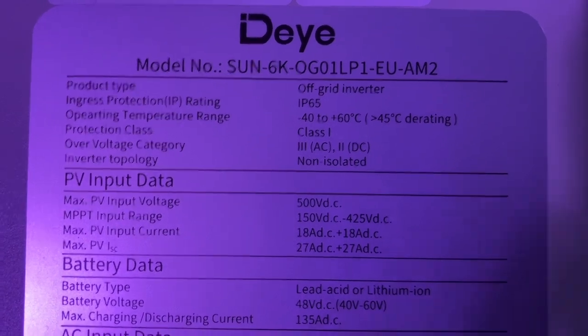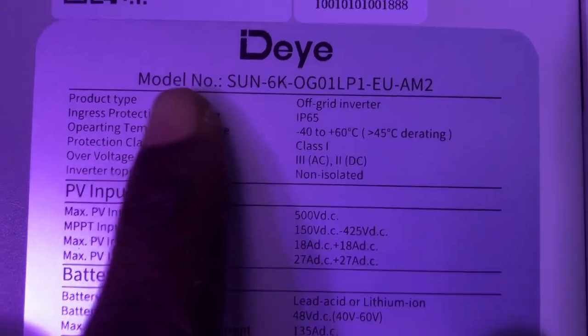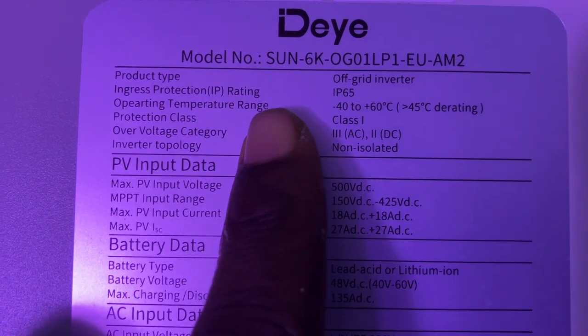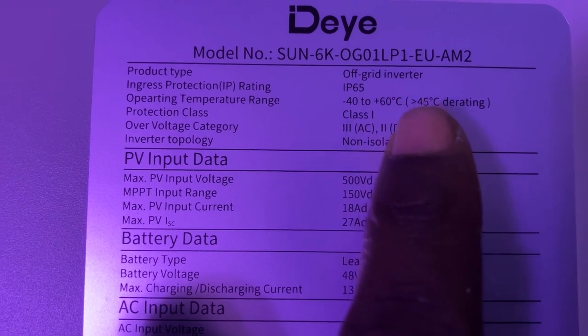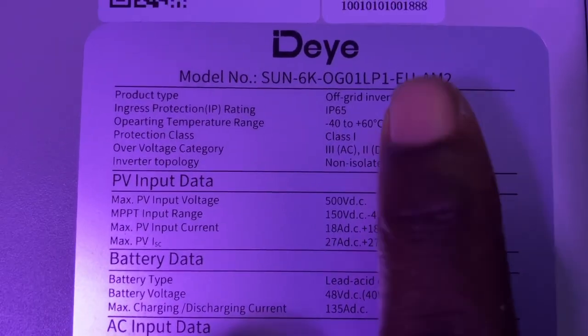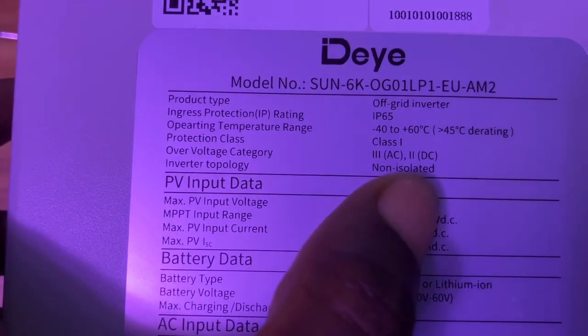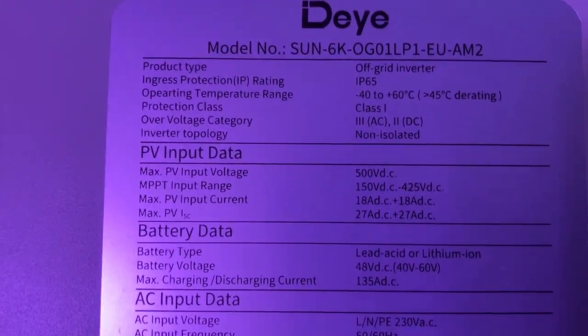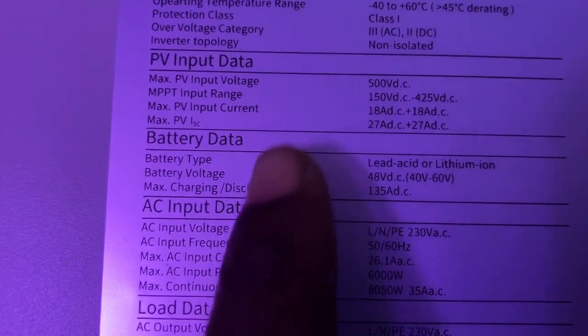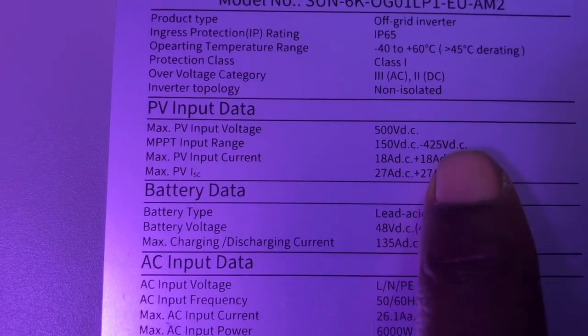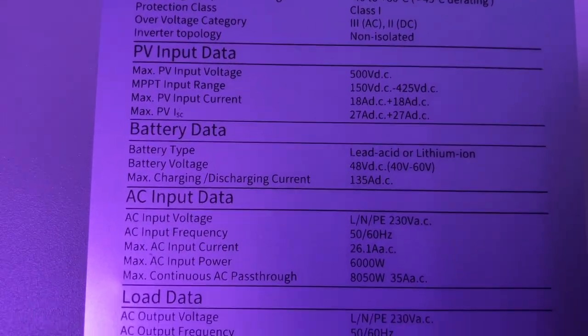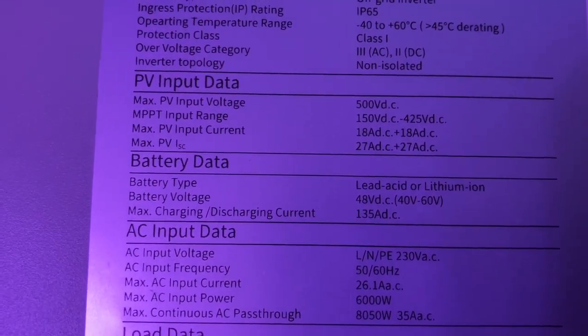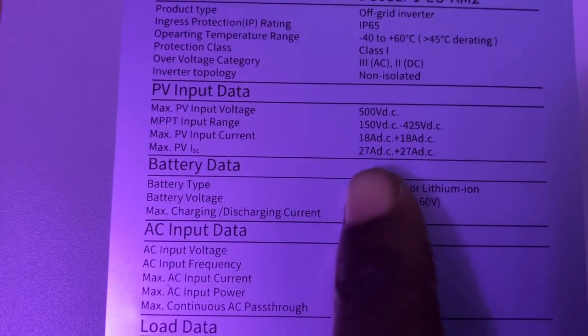A quick look at the specification. So you can see this is the model number, and you can see it has IP65 rating and is an off-grid inverter. So the working temperature here is minus 40 degrees to 60 degrees, and at 45 degrees the power will derate. Okay, so the protection class is class 1, and the overvoltage category is class 3 and class 2 for DC. PV input is 500 volts, and it needs 150 volts to 425 volts to operate, and the maximum input current it will take from the PV is 18. So even if you oversize this on each string, it won't take more than 18 amps.